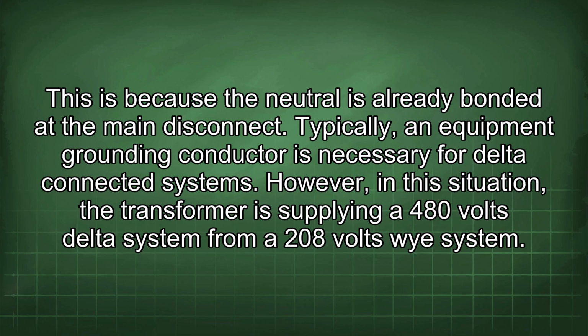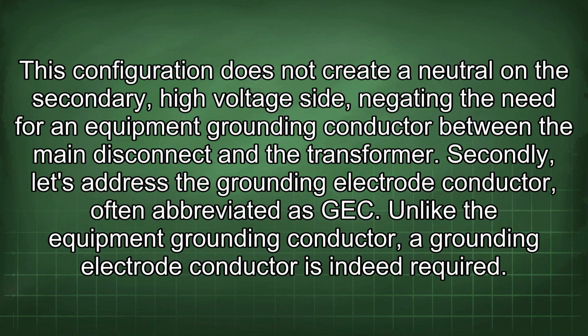Typically, an equipment grounding conductor is necessary for delta-connected systems. However, in this situation, the transformer is supplying a 480 volts delta system from a 208 volts Y system. This configuration does not create a neutral on the secondary high voltage side, negating the need for an equipment grounding conductor between the main disconnect and the transformer.